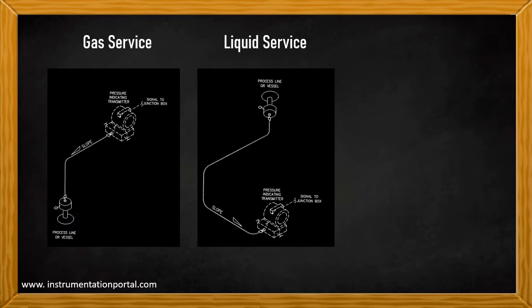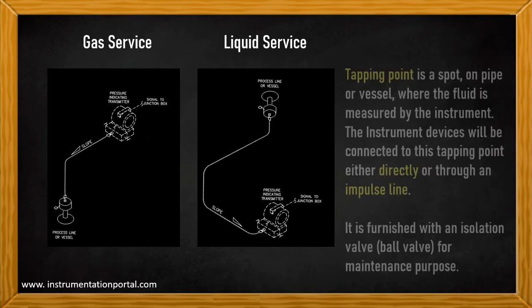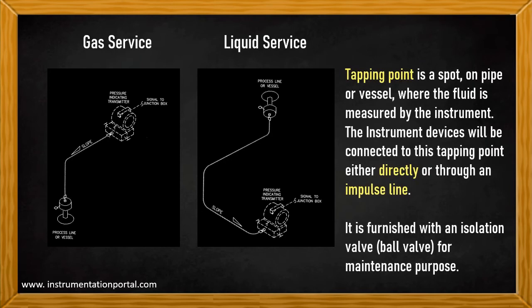This is the diagram of the instrument hookup. The left drawing is for gas service and the right drawing is for liquid service. As can be seen, the instrument position in gas service is higher than the tapping point, while in liquid service the instrument position is lower than the tapping point. The tapping point is a spot on a pipe or vessel where the fluid is measured by the instrument. The instrument device connects to this tapping point either directly or through an impulse process line, and the tapping point is furnished with an isolation valve — usually a ball valve — for maintenance purposes.